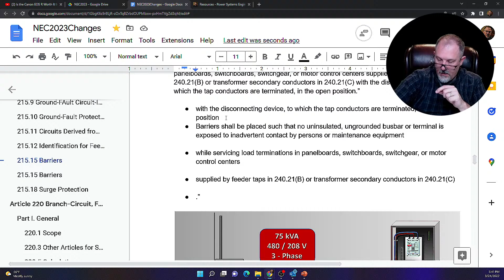Barriers shall be placed such that no uninsulated, ungrounded bus bar or terminal is exposed to inadvertent contact by persons or maintenance equipment. So in the case of me turning this to the open position, these primary lugs are energized. So I need to have barriers in this location such that no uninsulated, so that I cannot expose my electrical worker to a shock hazard.